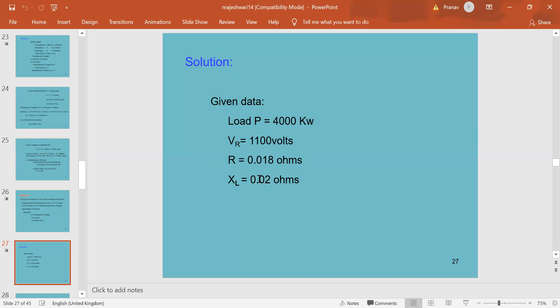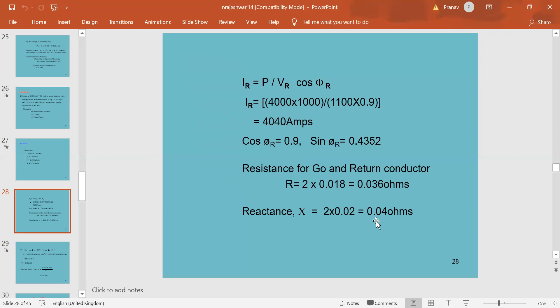So for this IR will be P by VR cos phi R. So IR is equal to 4000 into 1000, with 4000 kilowatts, that is 4000 into 1000 divided by 1100 into 0.9. So we will get the receiving end current as 4040 amperes, and cos phi R is 0.9, sin phi R will be 0.4352. Then go for resistance, and resistance for go and return conductor will be 2 times 0.018, which is equal to 0.036 ohms, and the reactance X is equal to 2 times 0.02, which is equal to 0.04 ohms for go and return conductors.